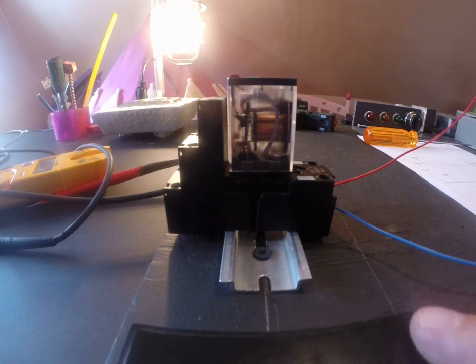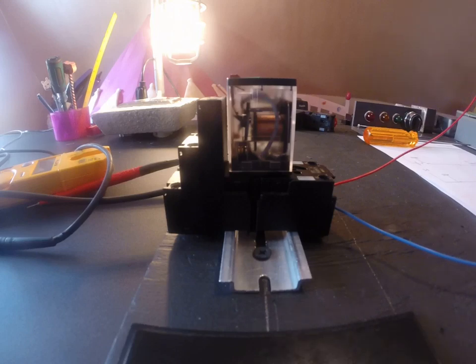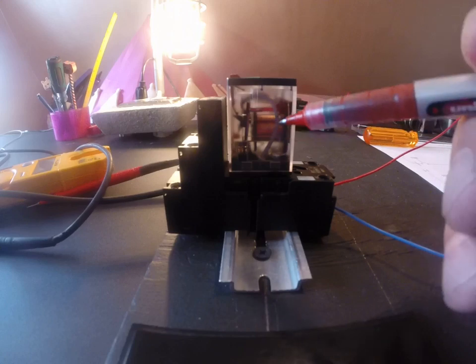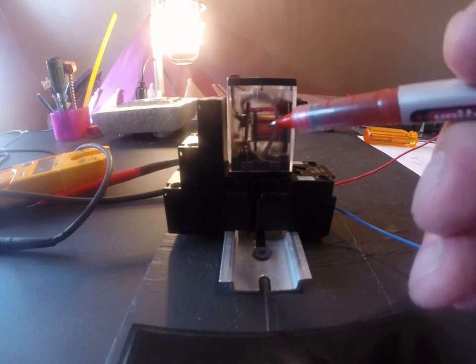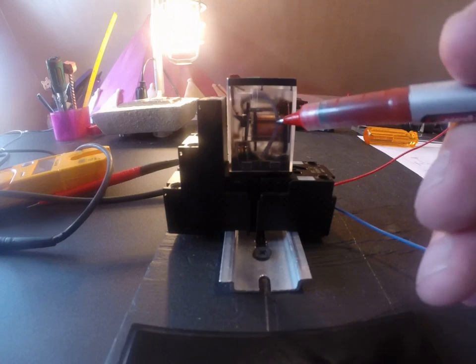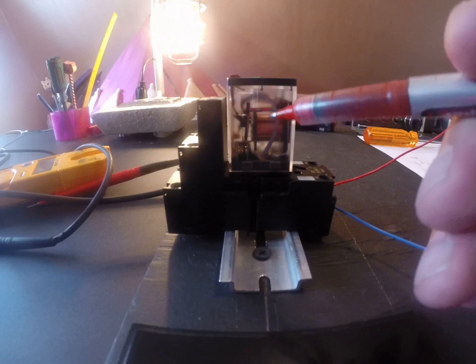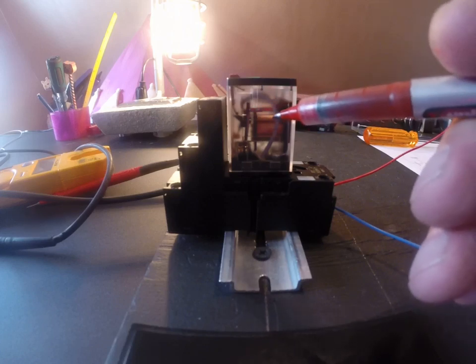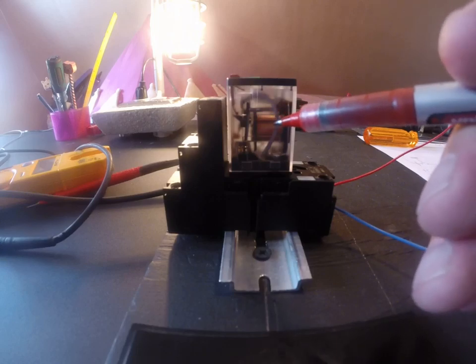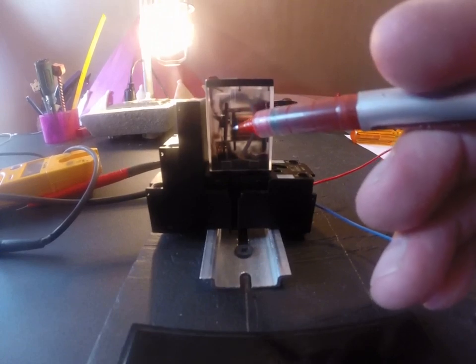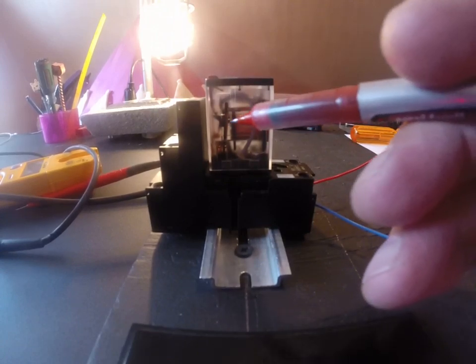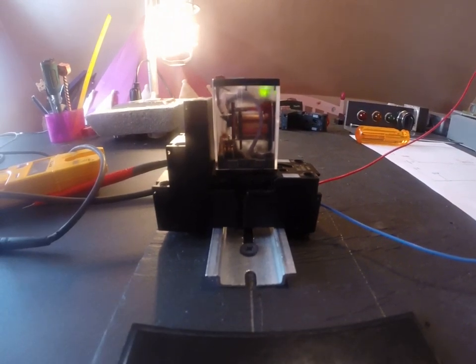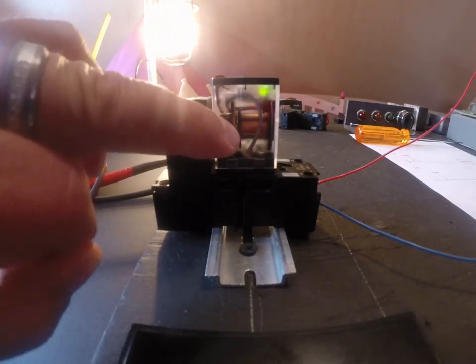Which is basically an inductor which is what you learned yesterday. When I energize or put current through this little wire that's got a lot of windings, if I actually unwound it it's probably several, probably 10 to 20-30 feet long of just wire around that coil, small wire. But when I put current through that wire one it creates a magnetic field. The more windings, the more turns I have around that core, the higher the magnetic field. The higher the magnetic field, the stronger my magnetism is. And this one's only strong enough, designed strong enough to pull this plunger down so that it can change state from normally open to normally closed and you can really see that gap closing.